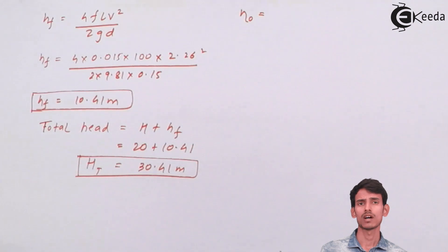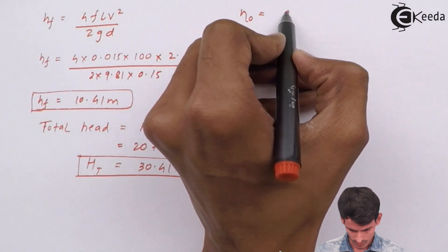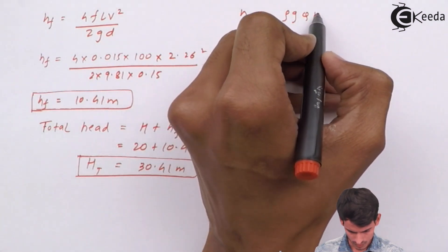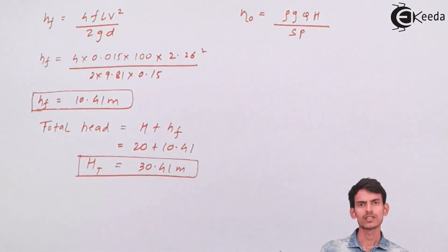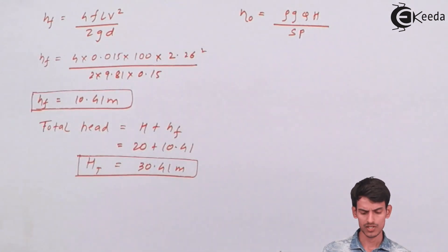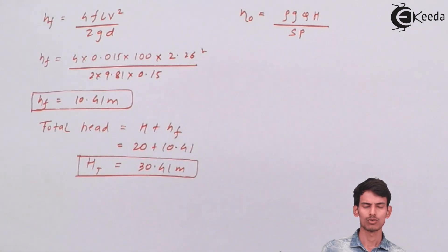Overall efficiency is nothing but the power developed by the impeller (or the pump) divided by the shaft power. Now we'll get the shaft power very easily because overall efficiency is given, the value of power developed (ρgQH) is known to you. Substitute everything in this equation and get the value of shaft power.